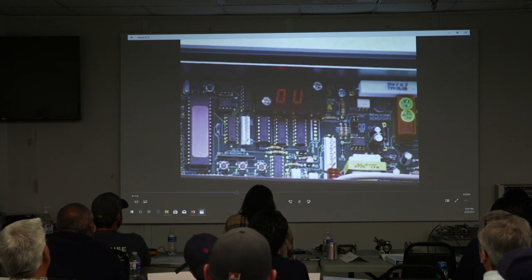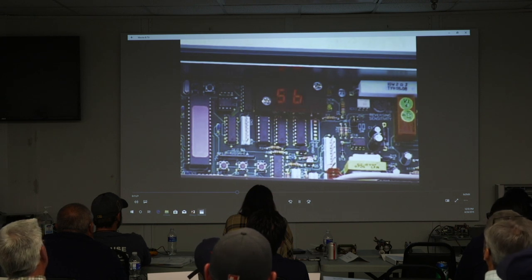If the door is not being held open by any devices, the cycle code will display briefly and then be replaced by the time delay display. If any of these devices are still active, that display will remain until the device clears. In the case of multiple devices, the display will alternate between all cycle devices. When the cycle code expires, the display changes to D1, which is the normal time delay.